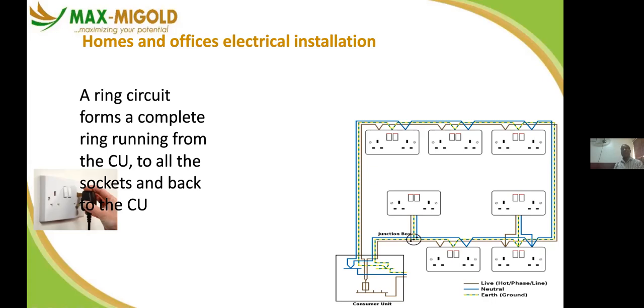So rather, we prefer the radial distribution, whereby you take supply from the distribution board straight to where the electric cooker is, or straight to where your laundry is, where you have the washing machine and your electric iron. So radial is from the distribution board to every point, but ring is looped along the line. We mostly discourage that because you don't really have control over it. You can overload the system while you try to loop them together. But radial is apples for apples, from the distribution board to where it is needed.